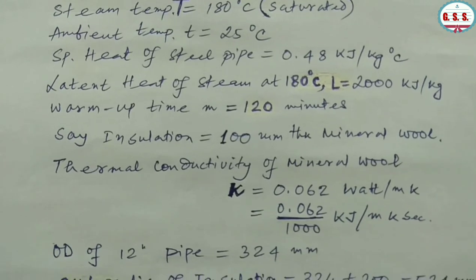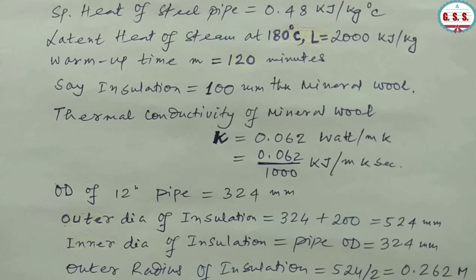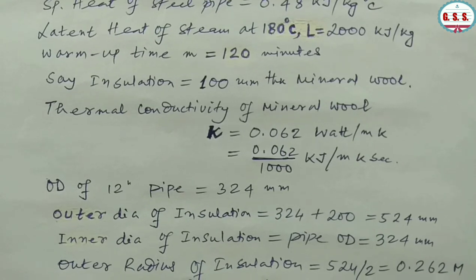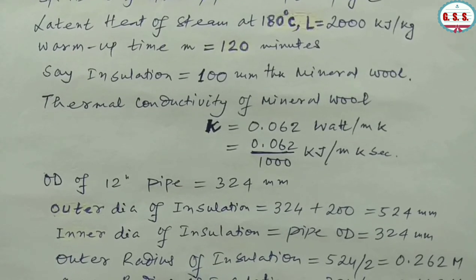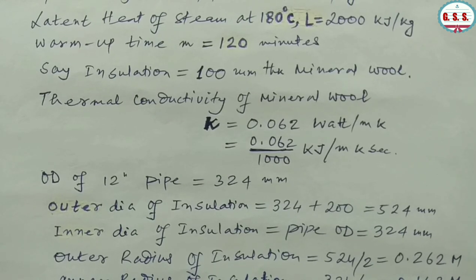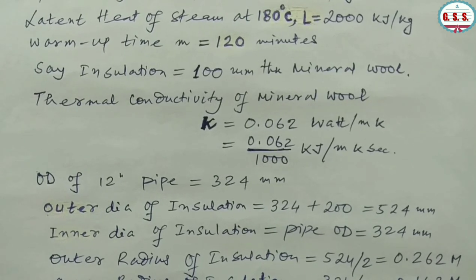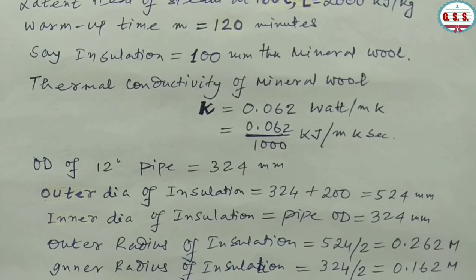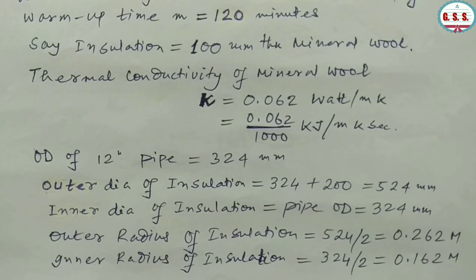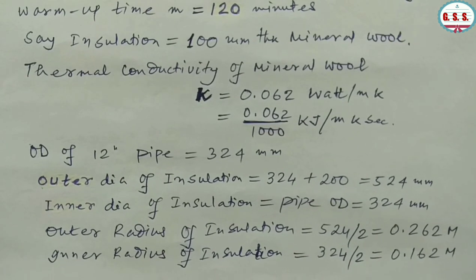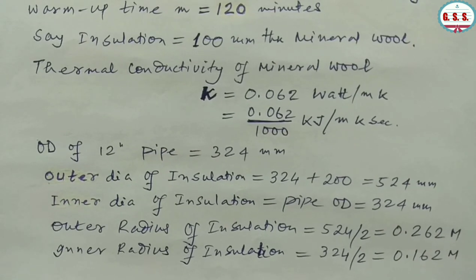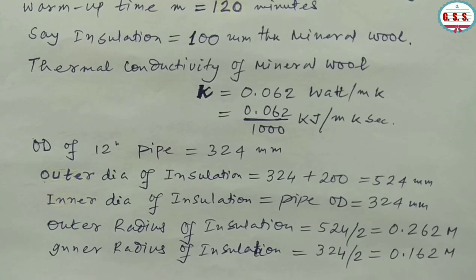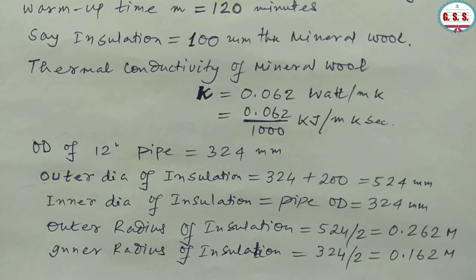Insulation thickness is 100 mm mineral wool. Thermal conductivity of mineral wool K = 0.062 W/(m·K), that is 0.062/1000 kJ/(m·K·s). Outer diameter of 12 inch pipe = 324 mm, so outer diameter of insulation = 524 mm. Inner diameter of insulation = 324 mm. Therefore, outer radius of insulation R0 = 0.262 m and inner radius of insulation Ri = 0.162 m.